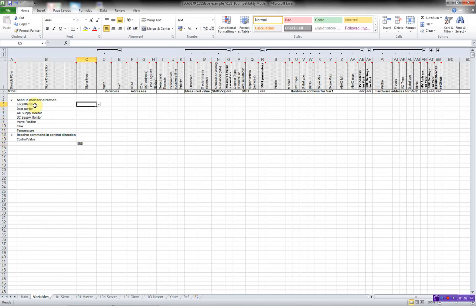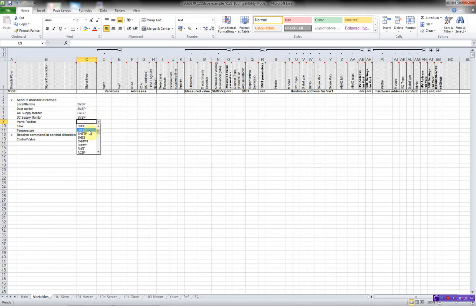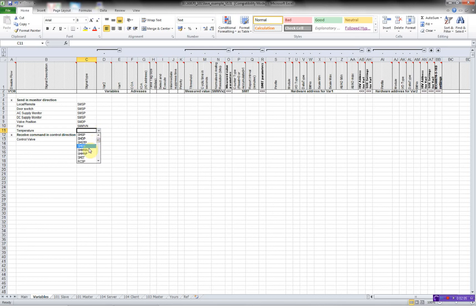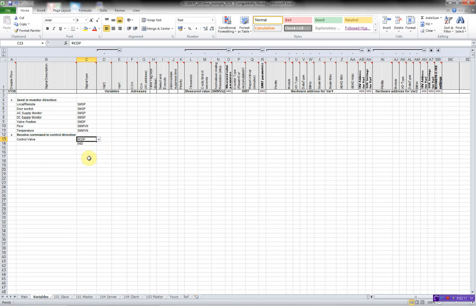The next thing to do is to specify the signal type. In this case, it's a single point. Double point for the valve position. For flow, it is a normalized measured value. And here it is a command double point.